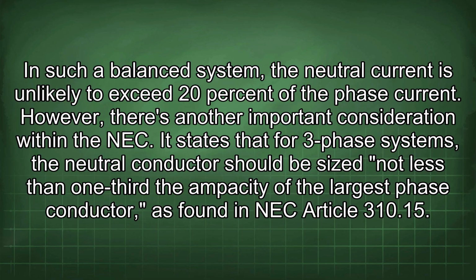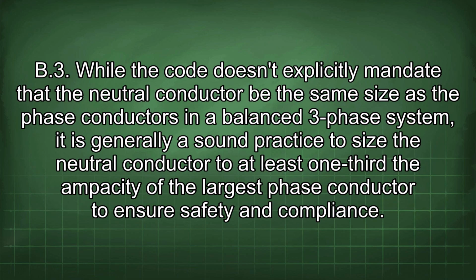However, there's another important consideration within the NEC. It states that for 3-phase systems, the neutral conductor should be sized not less than 1/3 the ampacity of the largest phase conductor, as found in NEC Article 310.15. While the code doesn't explicitly mandate that the neutral conductor be the same size as the phase conductors in a balanced 3-phase system, it is generally a sound practice to size the neutral conductor to at least 1/3 the ampacity of the largest phase conductor to ensure safety and compliance.